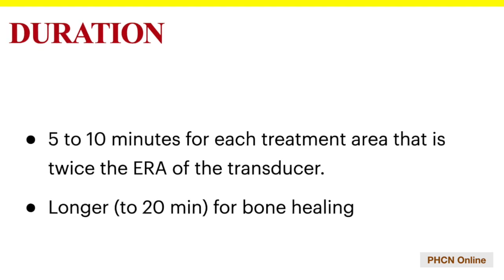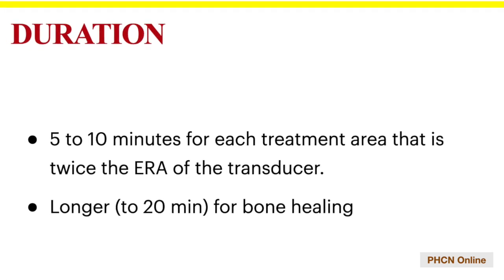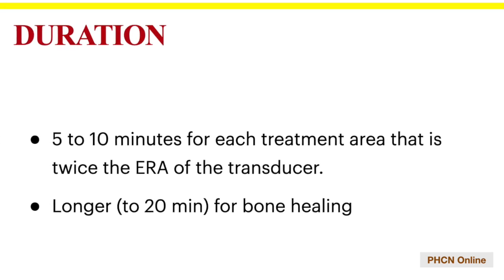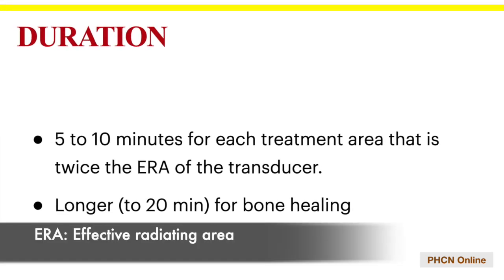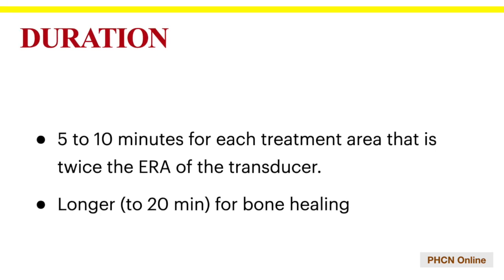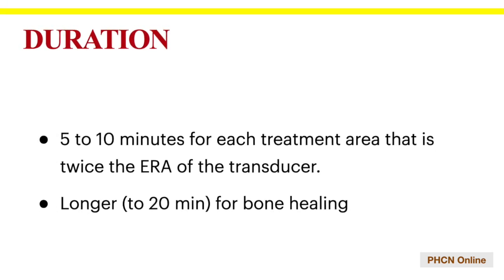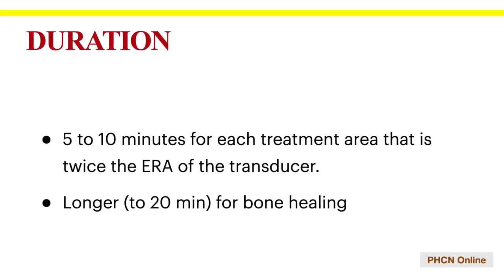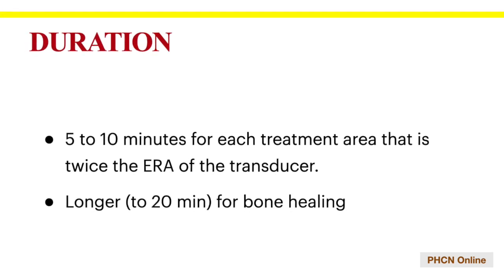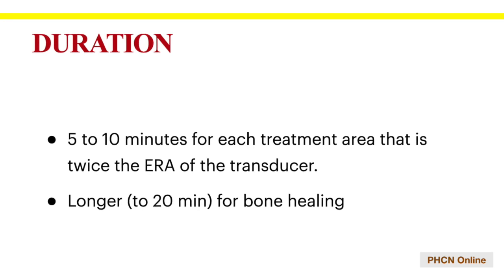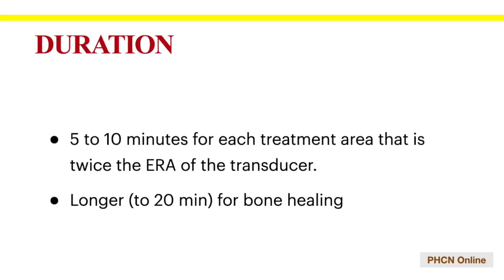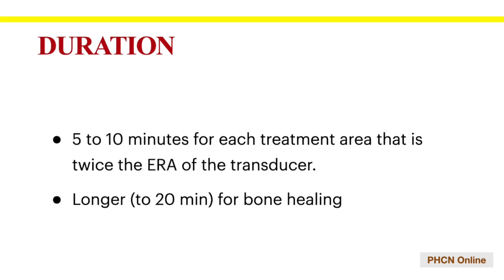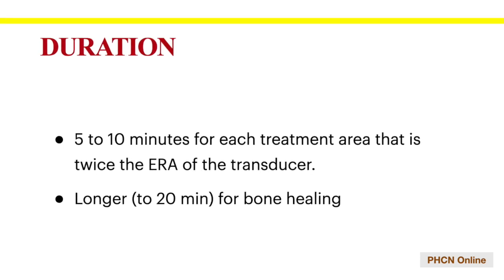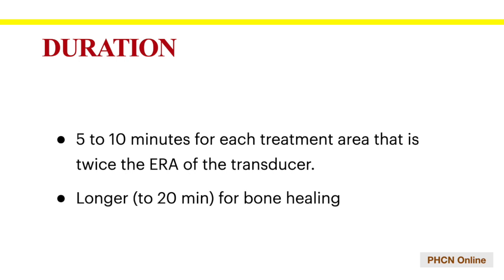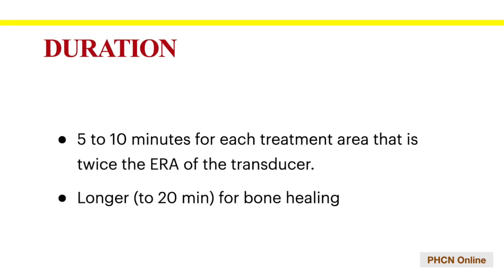Duration. Treatment duration is selected according to the treatment goal, the size of the area to be treated, and the area of the sound head. For most thermal or non-thermal applications, ultrasound should be applied for 5 to 10 minutes for each treatment area, that is twice the area of the transducer. In general, treatment duration should be increased when lower intensities or lower frequencies of ultrasound are used, when areas larger than twice the area of the transducer are treated, or when higher tissue temperatures are desired.